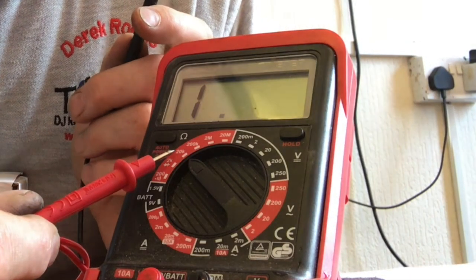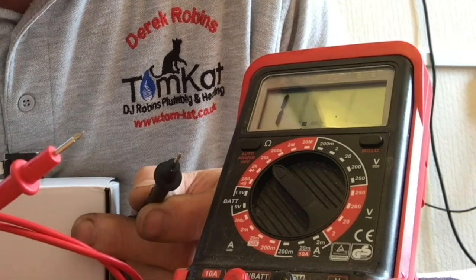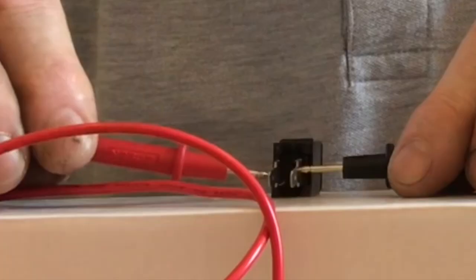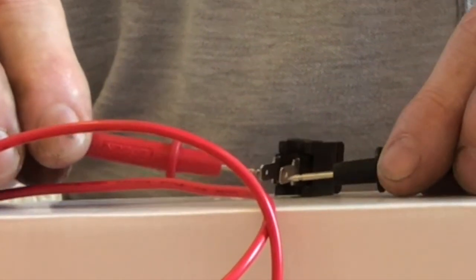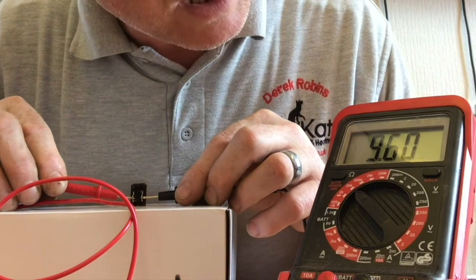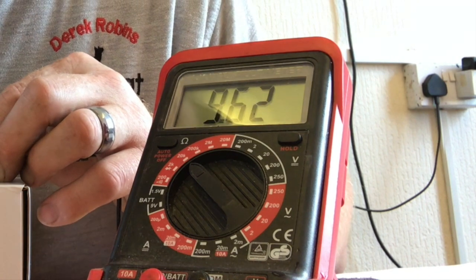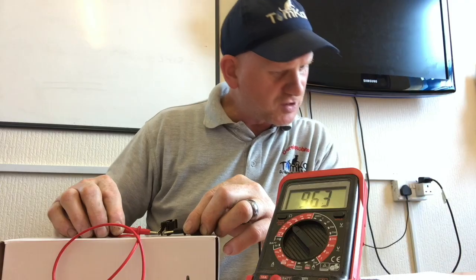Set your multimeter to 20k ohms. Check the screen changes when you touch the probes — confirming the meter works. Taking a reading on the NTC, it shows 9.62k ohms. According to the chart for 30 degrees it should be 9.78k ohms — so it's not far out.